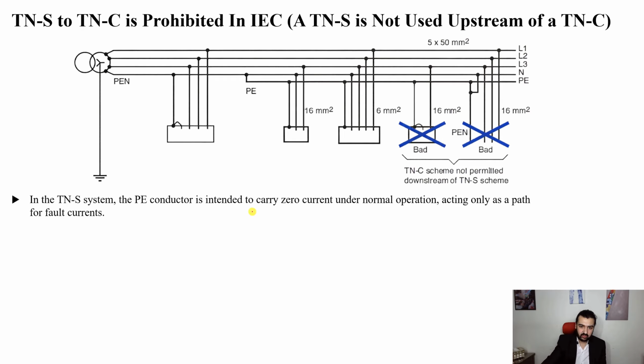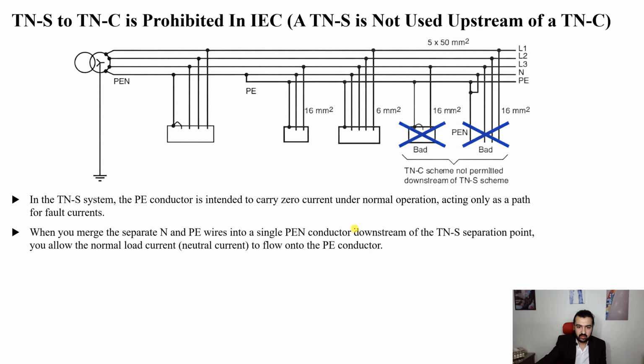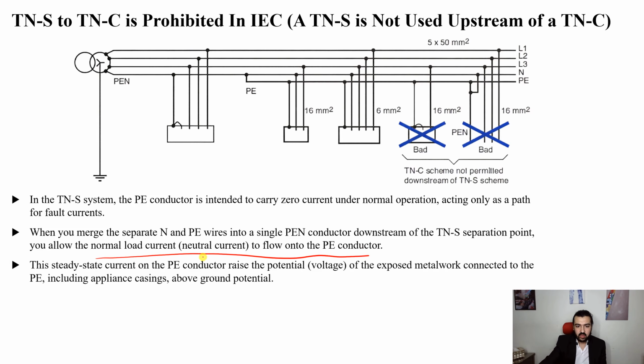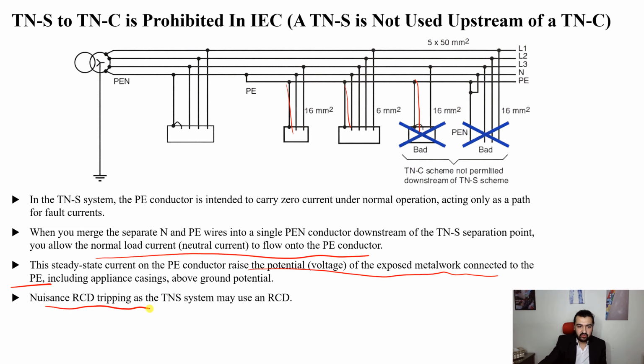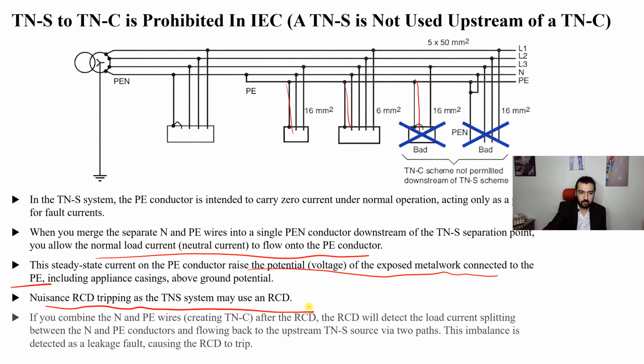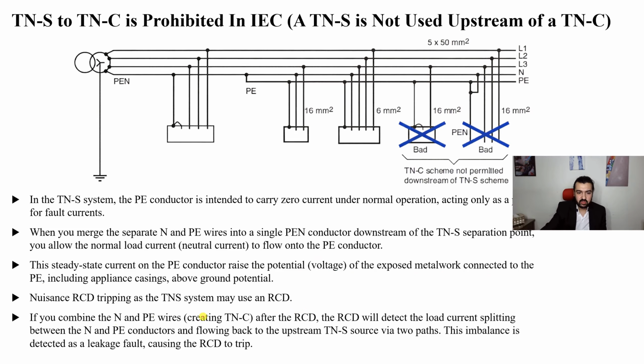So it has zero current under normal operation, protective earth, only a path for fault currents. When we merge them downstream of the TNS separation point, you allow normal load current to flow into the protective earth. This will cause or raise the potential voltage of the exposed metal wire connected to the protective earth. Anything connected to the protective earth will have the same voltage drop. Another thing that can cause RCD tripping, as TNS may use an RCD. If you combine N and P protective earth creating TNC after RCD, the RCD will detect that there is a difference due to the splitting of the current. Part of it, I1 and I2, is splitting at this point. This imbalance will be detected as leakage fault, causing the RCD to trip.